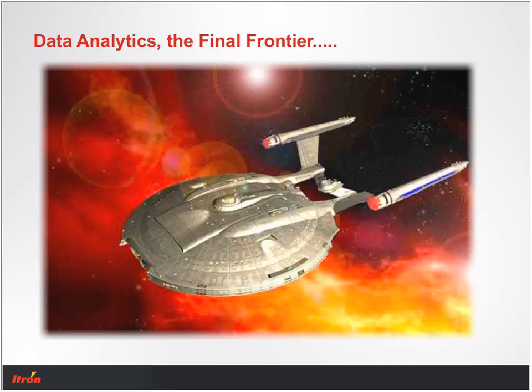That's not very effective. So what we're doing at Avista is working with Washington State University to develop a methodology that could understand the load makeup for every 5, 15 - we're not sure on the interval yet, 5, 15, or 30-minute interval - and determine the savings for that interval based on load flows for the actual measured settings versus load flows given the prior settings. We're working on that methodology right now, and it looks very good. We hope it will provide the kind of results we want and allow us to have a methodology that's acknowledged as accurate, so there's no ambiguity around the results.